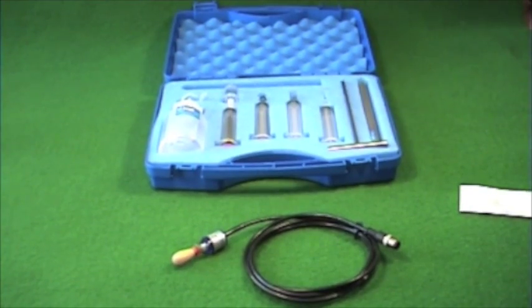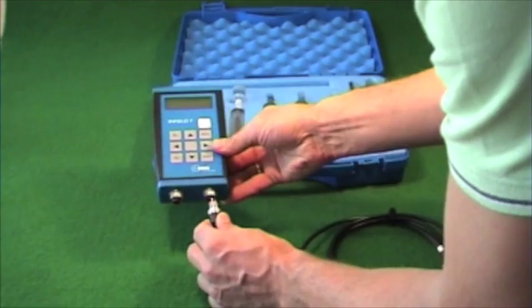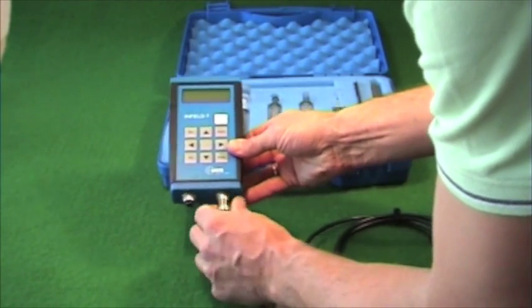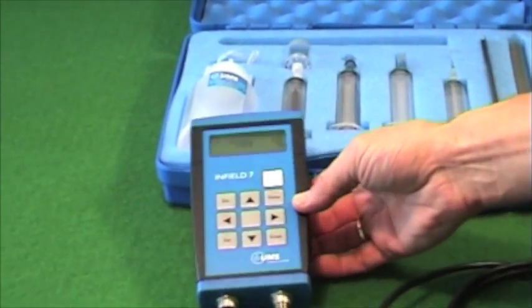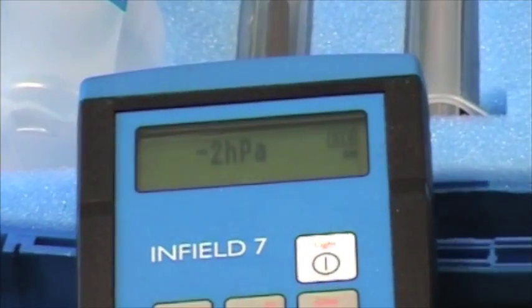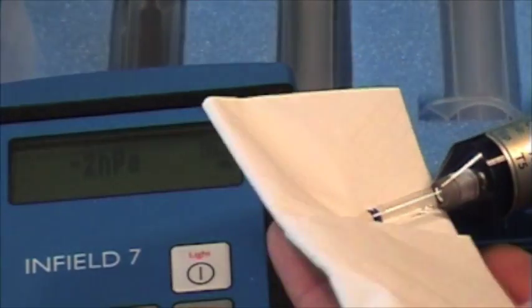To check the function or to refill you need a display unit like the Infield 7 handheld or a logger's display to see the values. Connect it and switch it on. Pull away the protection cup but avoid turning it. Now the value measured should be around zero.